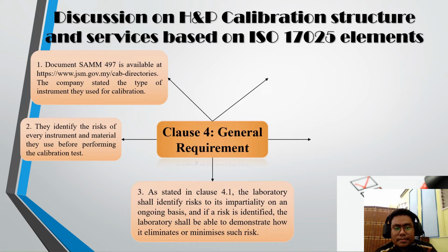So the third point is, as stated in clause 4.1, the laboratory should identify risks to impartiality on an ongoing basis, and if a risk is identified, the laboratory shall be able to demonstrate how it eliminates or minimizes such risk. So this statement shows that they need to identify the risk and plan how to eliminate the risk well. That is very important to make sure that all the processes in calibration tests go well on an ongoing basis.